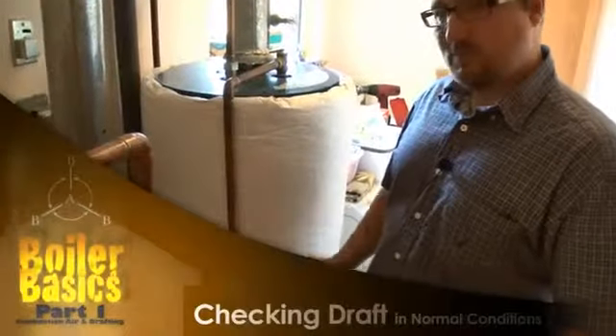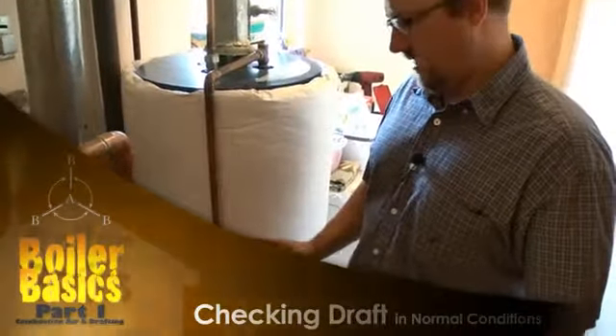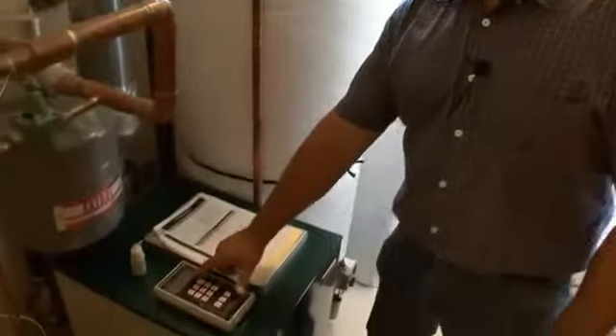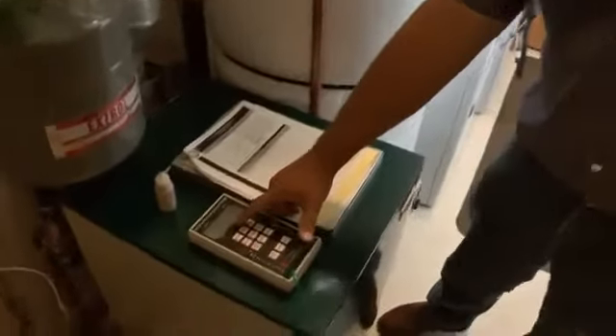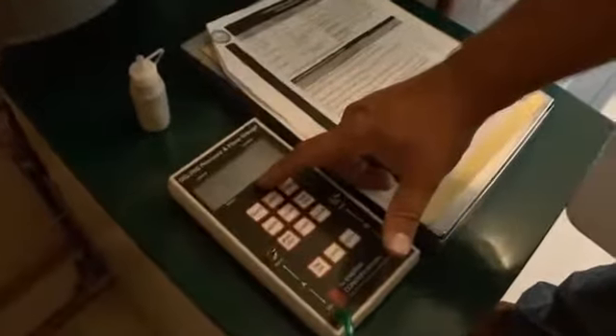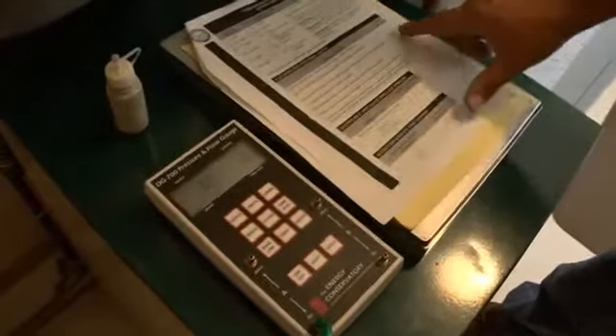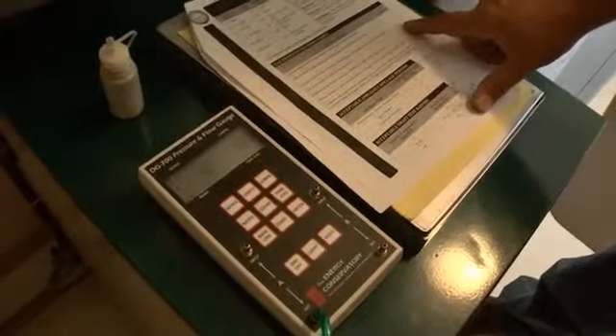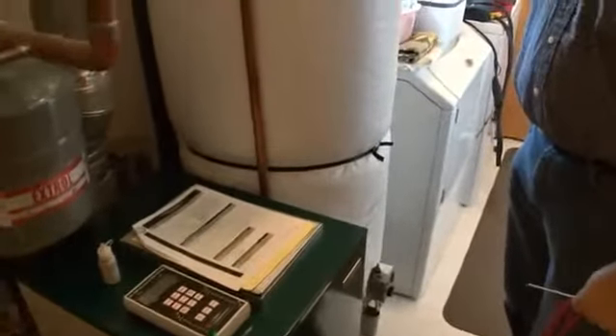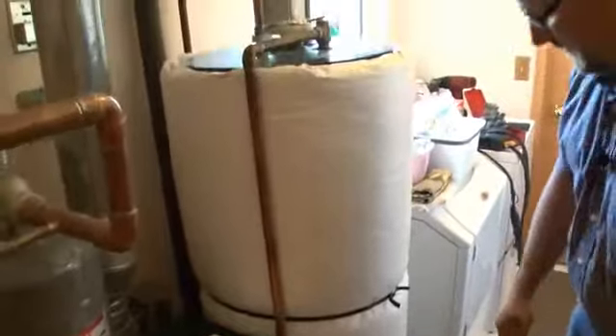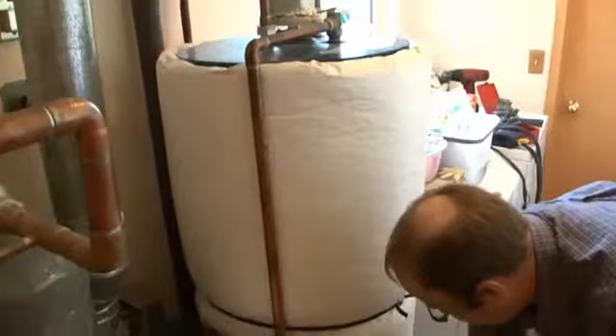At this point, we have all the doors open, the fans are off, and you can see our baseline pressure reading is definitely below the threshold. We're okay at this point, so we can continue. So at this point, we will get the actual draft reading from this water heater. We'll get the water heater fired.